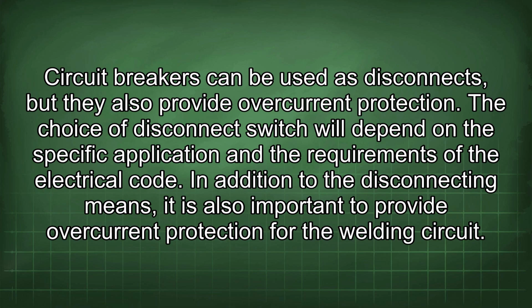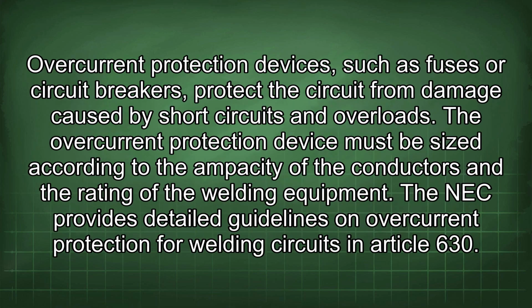In addition to the disconnecting means, it is also important to provide overcurrent protection for the welding circuit. Overcurrent protection devices, such as fuses or circuit breakers, protect the circuit from damage caused by short circuits and overloads. The overcurrent protection device must be sized according to the ampacity of the conductors and the rating of the welding equipment. The NEC provides detailed guidelines on overcurrent protection for welding circuits in Article 630.